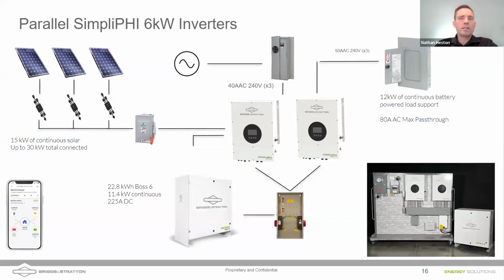So in this example that you can see on the screen, we only have a maximum of 80 amps of pass-through, and that's not enough to be able to power the whole loads panel of most homes. In an off-grid situation, you might be able to get by with a smaller amount of pass-through like this. And this is a good option for some of those smaller homes. In fact, just a single one of these inverters is what I'm running in my house here. And it's a good option for powering a subset of the loads of my home.